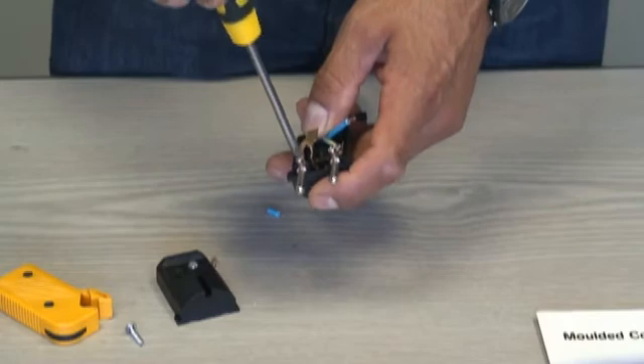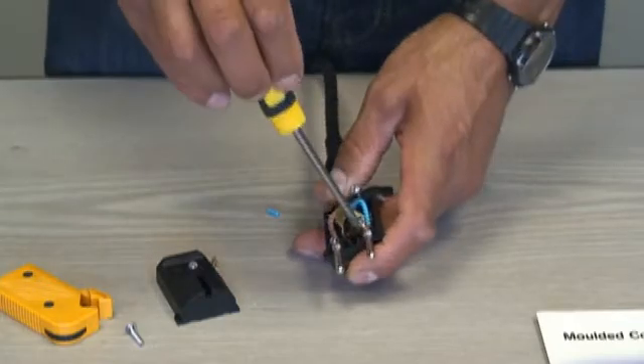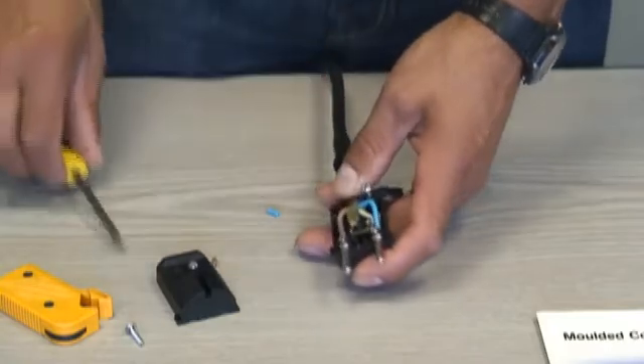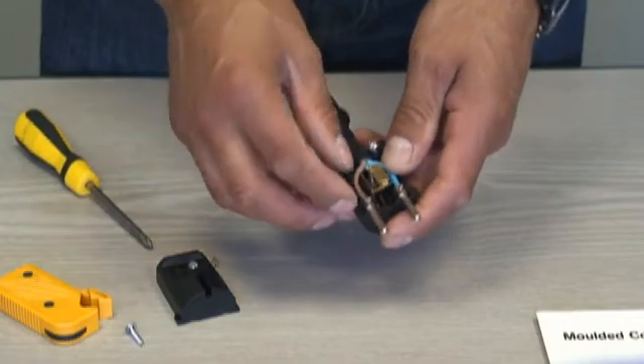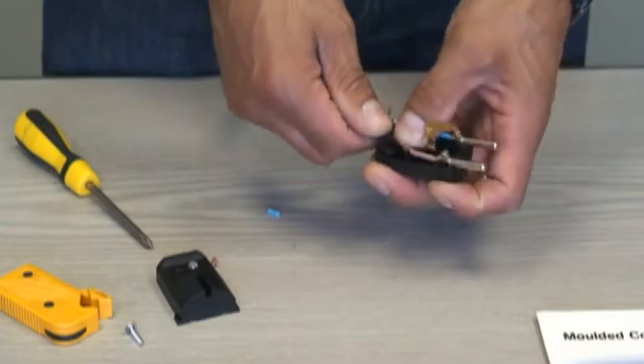Then with the other two, nice and simple, twist the ends up, post them in into the terminals and screw it up. Live in, remember live is brown. Neutral is blue. Like so. That's a good fit. You don't want any copper core exposed, you want to push it right into the PVC sheath. Nice and neat.